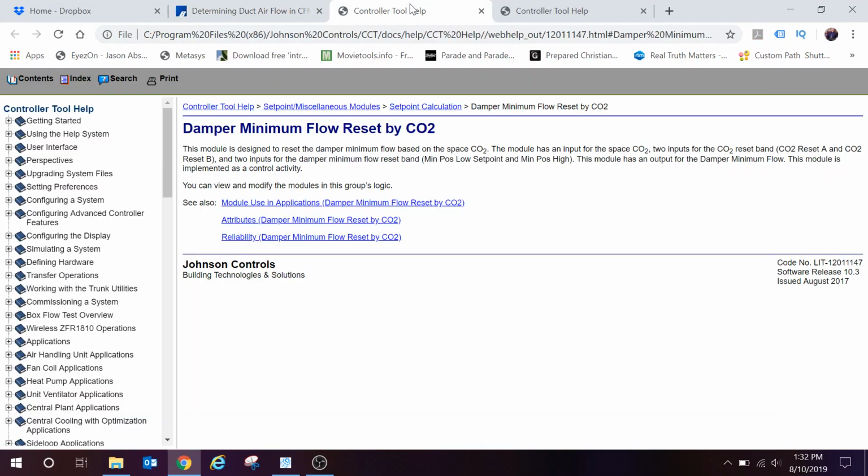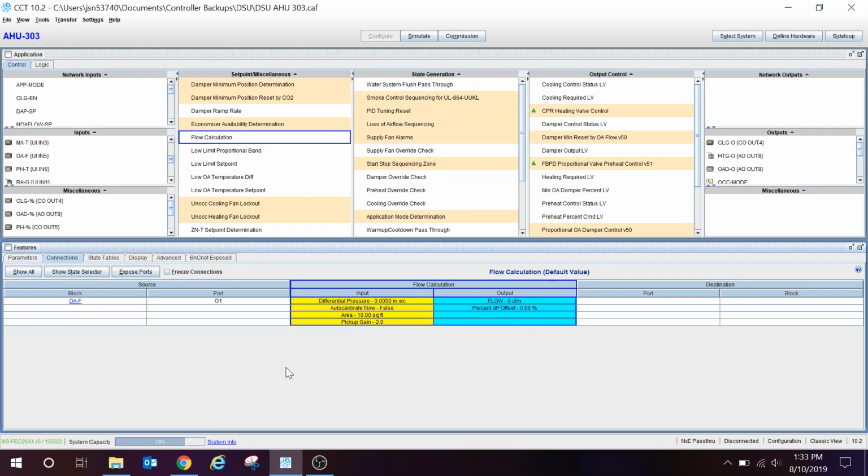One thing I would advise you to do, unless you have a lot of advanced measuring equipment to calculate this, is basically run the numbers yourself. Get your conversion chart out and know what your airflow is, know what the velocity pressure is coming from your sensor, then calculate it and compare your calculation to what you see on the system. That's going to give you an idea if you are anywhere close. Again, there are some ways to manipulate it to get the numbers to where they need to be. If you do have good measuring equipment that you know is accurate, you can compare it to that.